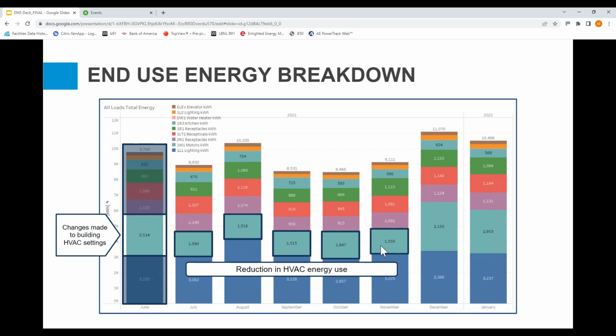What we ended up doing is we found a couple things: the heat recovery ventilators were running 24/7, not to the building schedules, so that wasn't right, and we adjusted that. We also noted the radiant floor set points were a lot higher than they needed to be, so we made adjustments there too—some pretty easy changes. What I really enjoyed about this was that because the facility staff was involved, they were the ones who really came up with these efficiency measures.